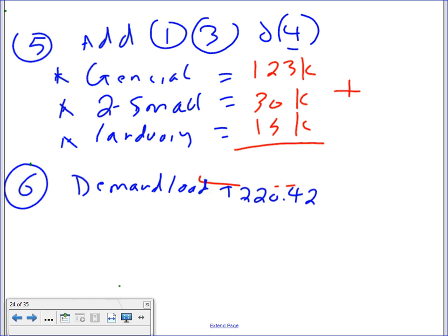When you do your math, you're going to find 168 kVA. Add them up. Then you apply the demand factor. Demand factor, 220.42. The code says it's highly unlikely all of them will be turning their lights and receptacles on at the same time. Right, for all these 10 units, unless they're having a big party that day, that everyone in the apartments is having a party, or unless you have 10 kids in every apartment.